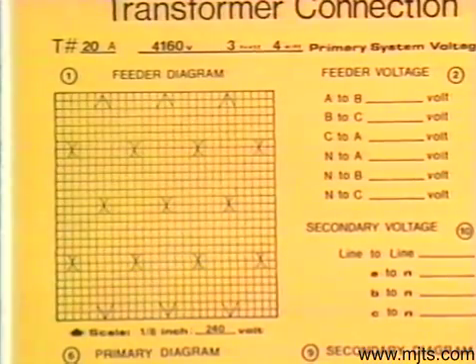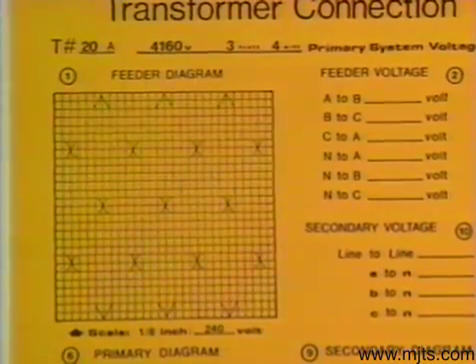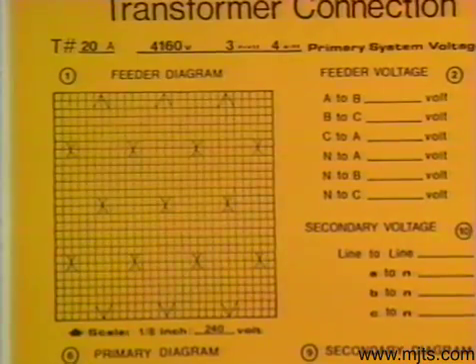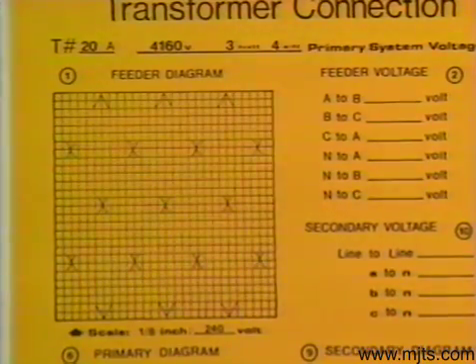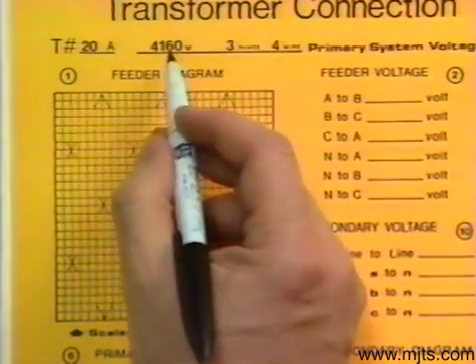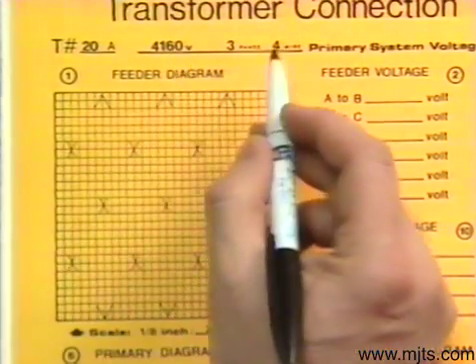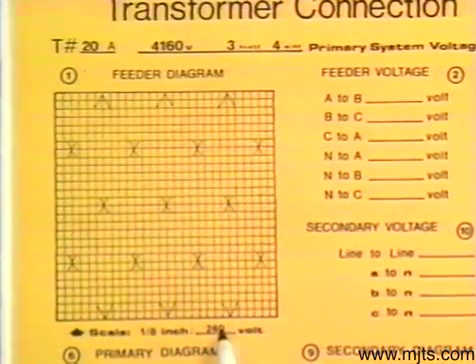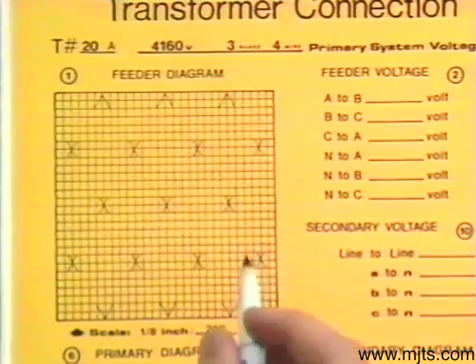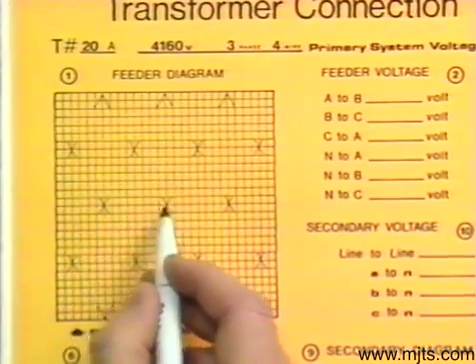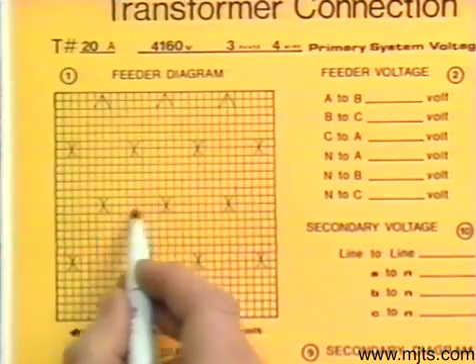Follow along on your step-by-step instructions in your information sheet. The first step is to diagram our feeder. Our feeder here is 4160 volts, 3 phase, 4 wire. We know the phase-to-phase value is 4160, and because it is a 4-wire system we know it is Y. We have a scale of 240 volts, and because we have a Y diagram, each of those vectors will represent 2400 volts.